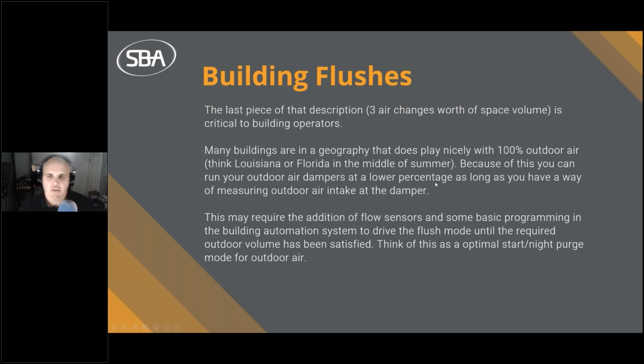Now, many buildings in a geography that doesn't play nicely with outdoor air, think Louisiana, Florida, in the middle of the summer, right? Highly humid, highly hot environments. Because of this, you can actually run your outdoor air dampers at a lower percentage as long as you have a way of measuring outdoor airflow intake. So if you have flow sensors at the outdoor air damper and you're sensing outdoor airflow, and those sensors are accurately calibrated, then you just do some logic math with an accumulator in your programming and you calculate that up. And once you have hit that threshold where you've brought in enough airflow, then you can start to lower back down to ASHRAE 62.1 standards.